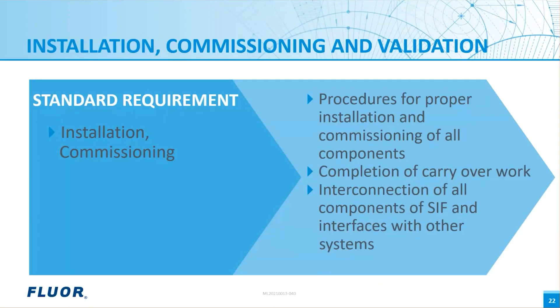Post-installation and commissioning, validation of SIS is performed as per the approved procedure to ensure that the installed system meets the functional requirements. Completion of validation is a critical milestone in the life cycle of the system before the plant startup. Validation for the SIS includes all the tests for the SIS, including testing of interfaces, interaction with BPCS, sequence checks if applicable, and operation of all bypass, overrides, and reset functions.